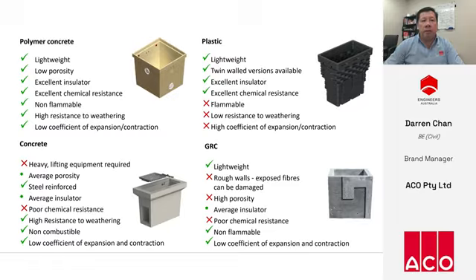Concrete is another option, and pits are reinforced with steel to give them strength. These are heavy but strong and non-combustible. GRC is glass reinforced concrete. In aggressive environments, thin wall GRC is prone to deterioration, particularly in alkaline soils. So GRC pits require regular maintenance and in some cases are susceptible to early failure. It's also a porous material, so really not the best option for electrical enclosures.